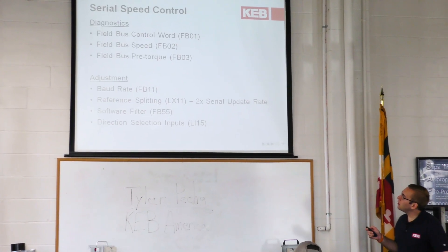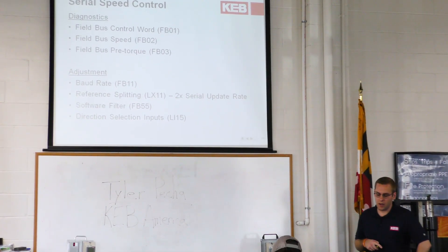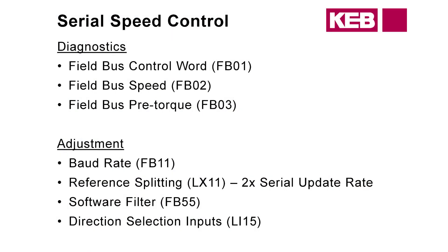So we've got the control word coming over — FB-01 will tell you what the control word from the controller is doing. Field bus speed is FB-02, that raw value. Field bus pre-torque is in a percentage. For ride quality adjustments, we have two parameters: reference splitting and the software filter. The baud rate is the communication rate between the controller and the drive, and it needs to be set the same on both. Then there's the direction selection inputs, which dictate what kind of hardware direction inputs from the controller the drive is looking for.